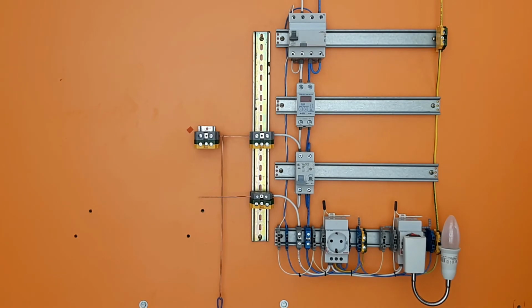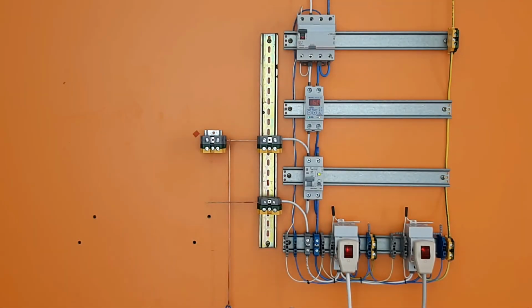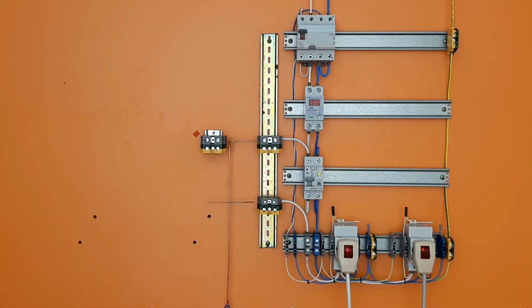Let's go further. Increase the current and enter the operating range of the AFDD. Let's make sure that the data obtained is reliable at current of up to 6 amperes. We will also check at the upper limit of the permissible current of conventional outlets. Everything repeats. The AFDD does not work. Our device provides an instant response.